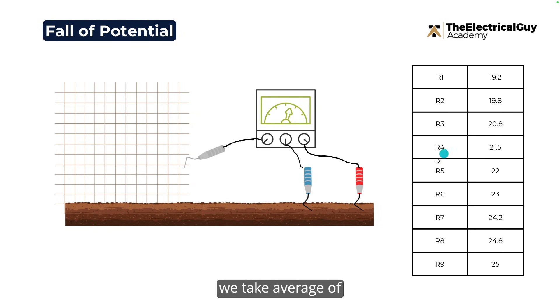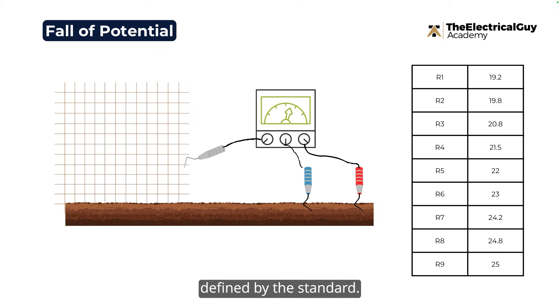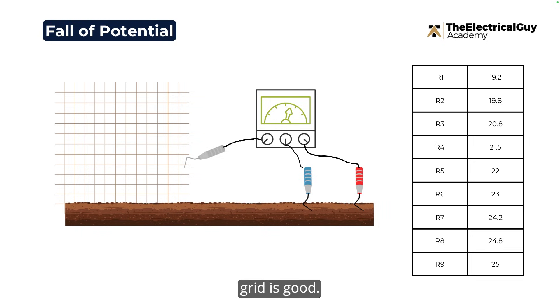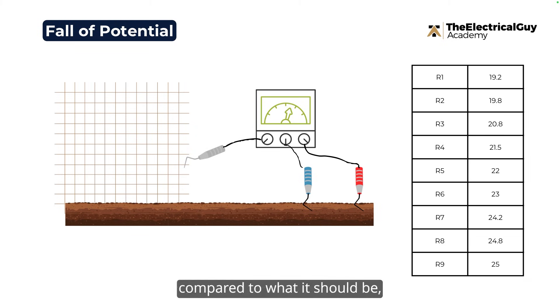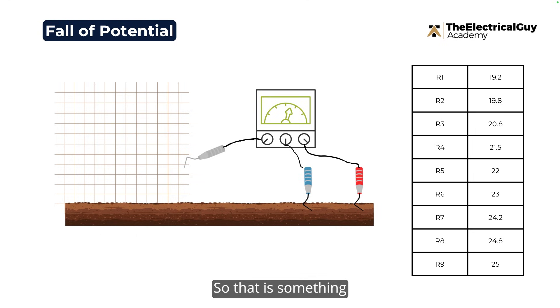Once we have all the readings, we take the average of the middle three or four values. That average resistance should ideally be less than the values defined by the standard. If it is, the health of the earth grid is good and the impedance is low enough to handle fault current. If the resistance is higher than it should be, something is wrong — maybe the earth grid is broken somewhere, or there is corrosion.